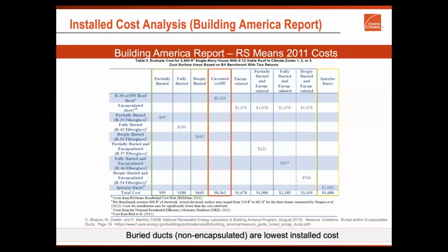The one thing I do always recommend, if a builder does decide to do buried ducts, is put the ducts in first, because they don't have to jump over pipes. They don't have to jump over a bunch of electrical cords, cables, conduit. It's all out of the way. The ducts are where they need to be. That's what we're focusing on, because that's what's causing the energy efficiency. That's what's causing the comfort, right? So all these callbacks that they deal with, if they focused on just the buried duct situation, and then added things later, it's much easier.